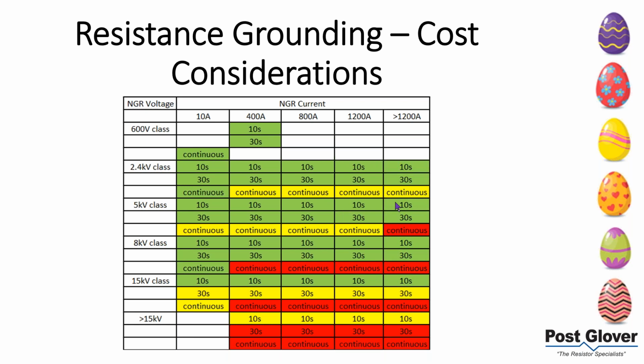So when I talk about how you're probably going to be using a reactor, or a zigzag instead of a resistor, a lot of the time it's because of these red boxes. At these voltages, it's more prohibitive in cost and size to use a resistor, so the benefits aren't necessarily worth the cost. This is where we see issues with resistance grounding for both generator protection and larger applications. And for wind and solar, a lot of the time the common values go from 690 volts, all kinds of different voltages, 6.6 kV, all kinds of different values. But once you're getting to the 20 and 30 kV, which is not that common, that's when it starts to become more difficult. So I just want to make sure you have a good visual of what that looks like.